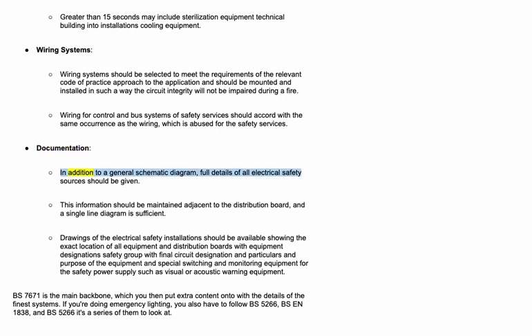Documentation. In addition to a general schematic diagram, full details of all electrical safety sources should be given. This information should be maintained adjacent to the distribution board, and a single line diagram is sufficient. Drawings of the electrical safety installation should be available showing the exact location of all equipment and distribution boards with equipment designation, safety group with final circuit designation, and particulars and purpose of the equipment and special switching and monitoring equipment for the safety power supply such as visual or acoustic warning equipment.